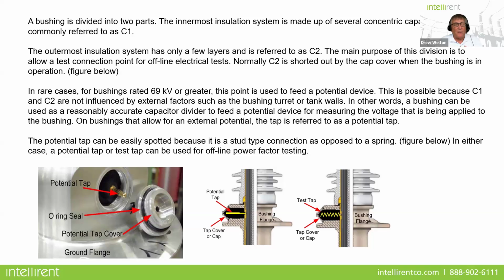The potential tap can easily be spotted because it's got this stud that you can connect to when the bushing tap cover is off. The other type, the test tap: both of them can be used for testing. But on this particular one, you'll see a spring, and when the tap cover is on, the spring is grounding out this tap. So either of these two are suitable for measuring power factor.